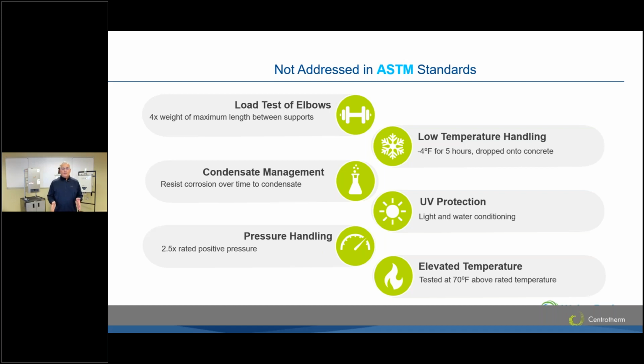So if we're at 50 degrees and lower and that pipe's been sitting out in the yard for days or weeks, it's gotten brittle. And when we're banging it around like that, we are putting cracks in that pipe, micro cracks. Well, that's not going to help us. That's not going to help us in our venting. Oh, I'll cut that end off. Hopefully you cut off enough. Who can tell you how much to cut off? So we have to be aware of things like this.